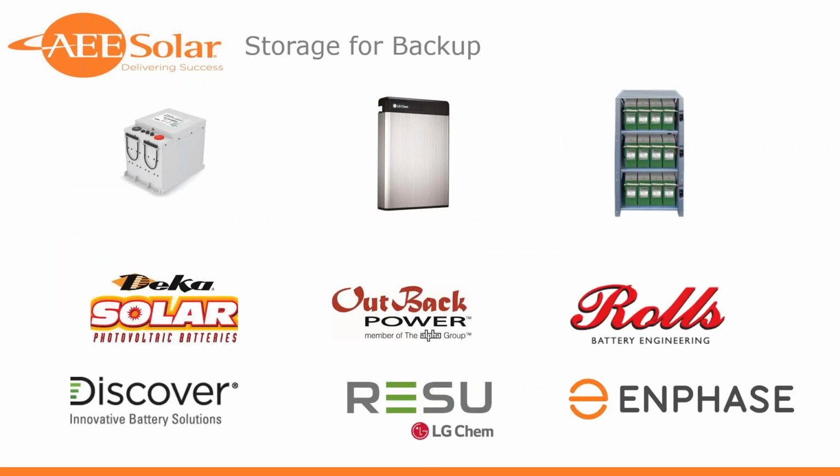On the actual chemical storage part of the backup application, again, some of the considerations, you're going to need product that's comfortable with being in a float application. So something that hopefully has good tolerance for that, with real low float amps. Some options here, we carry a full variety of Deka. So Unity 1, Unity 2. The Outback, I've got here on the upper right, the new PLC, the new pure lead carbon solution from Outback, and I'm hearing that there's a new battery coming out that may even actually be a little better suited to a backup application than the pure lead carbon.